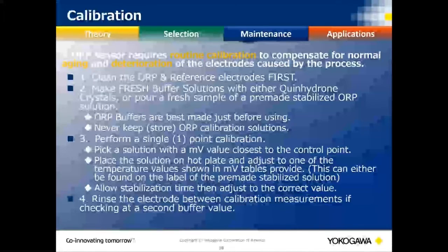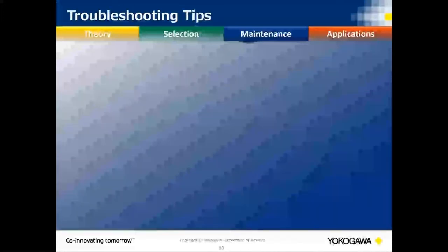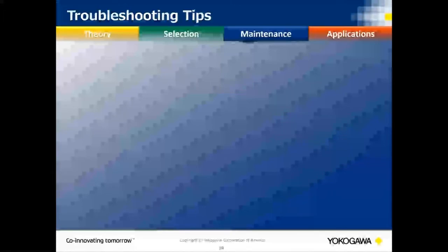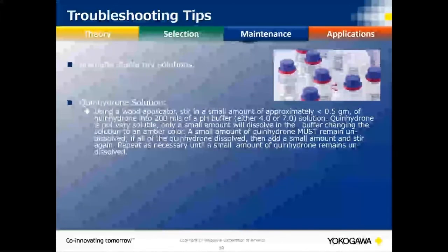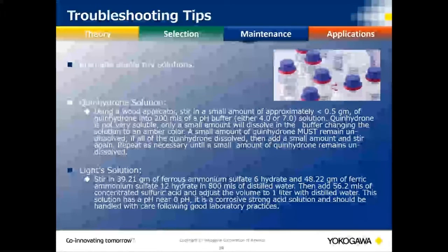Clean and rinse your probe, then make a fresh buffer. Historically this is done by mixing quinhydrone into your pH 4 or pH 7 buffer solutions — add a little, stir it in, and if it dissolves completely, add a little more. This combination has a known millivolt value at a given temperature. Alternatively, you can use pre-made single-use packets. Pre-made solutions like those from Hamilton are increasingly preferred. The Light's solution mixture is no longer used due to toxicity concerns.